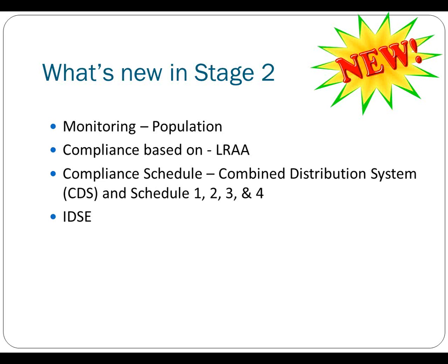Most of the systems that have populations less than 10,000 were granted a very small system waiver if they had a population less than 500, or a 40/30 certification. The 40/30 certification was granted if a water system had 2 years of results that were less than 40 TTHM and less than 30 HAA5s. So for most systems, that compliance was completed seamlessly, yet sampling under stage 2 will need to start beginning October of 2013.